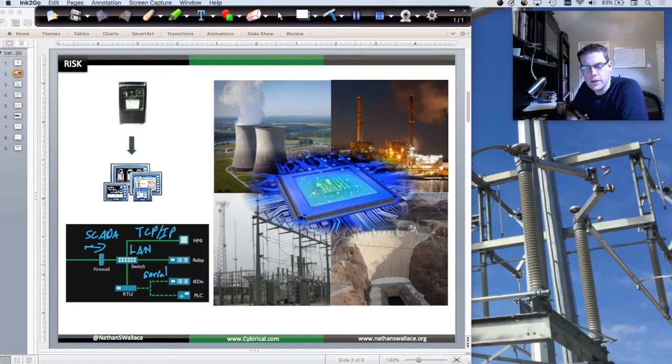So this could be vendor specific, this could be general, different protocols as far as, let's say, even Modbus. So that communicates with the RTU, and basically this RTU kind of acts as a protocol converter, even pass-through, so you can encapsulate some communication into Ethernet. So this RTU will serve that function. So, a lot of capabilities.